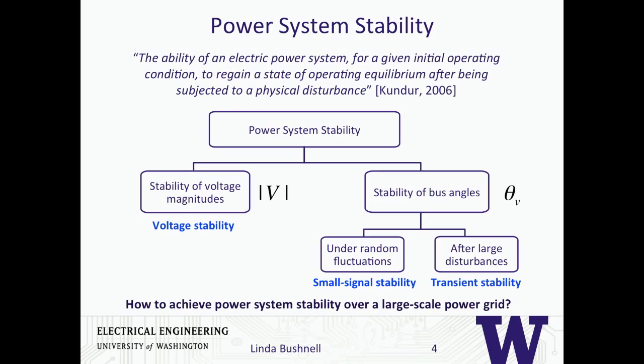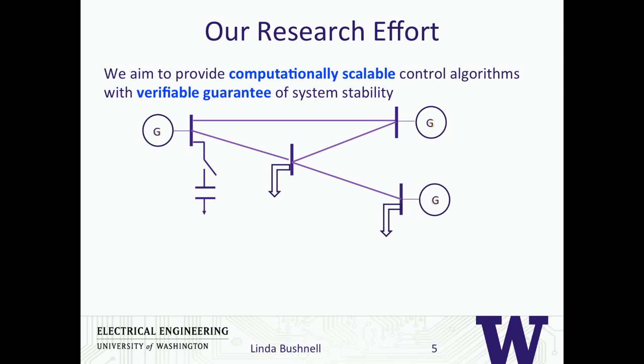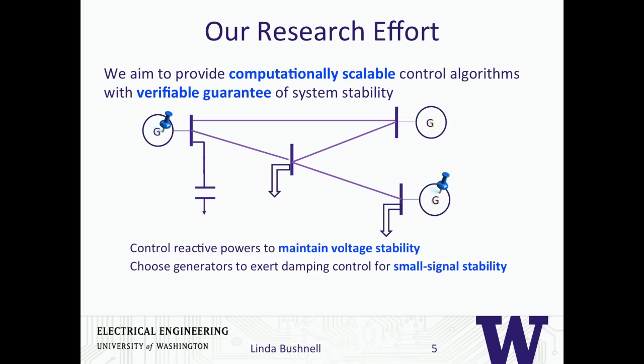Our research effort is focused on coming up with computationally scalable control algorithms, and we want to make sure we have verifiable guarantees for these algorithms. Looking at a power system with generators G and buses with loads — one problem for maintaining voltage stability is switching in a capacitor for a generator to maintain voltage stability. The other one is choosing generators to exert some control to damp the small signal phase instability. And then the third problem is if there's a big disturbance, you want to start shedding loads — which loads do you actually shed? That's the transient instability problem.